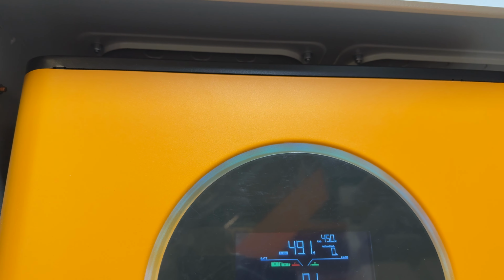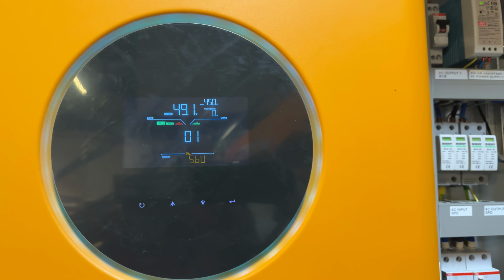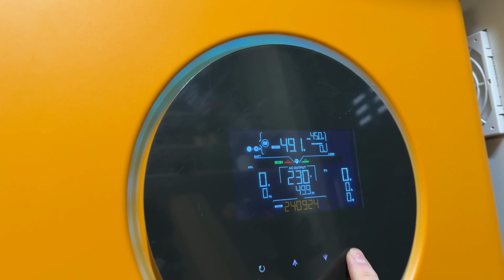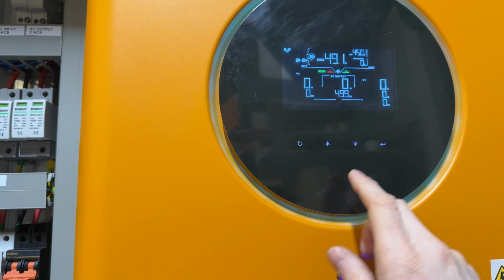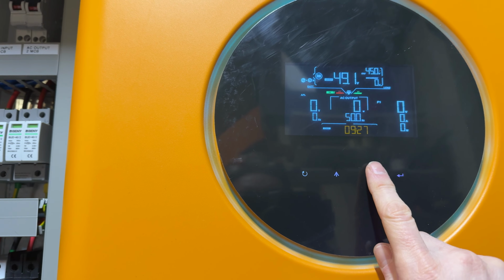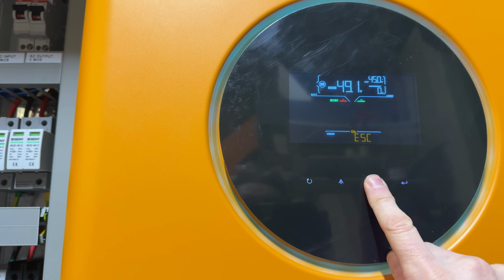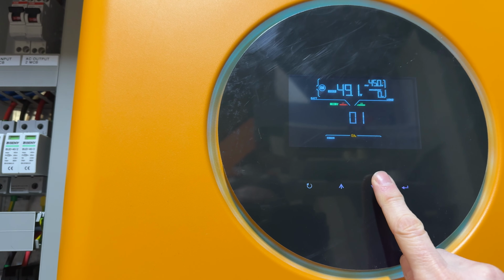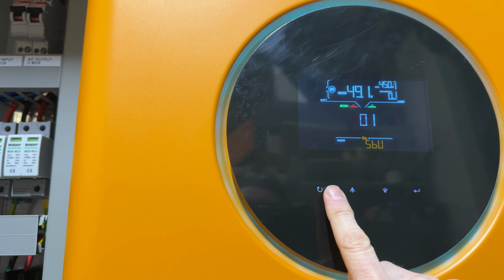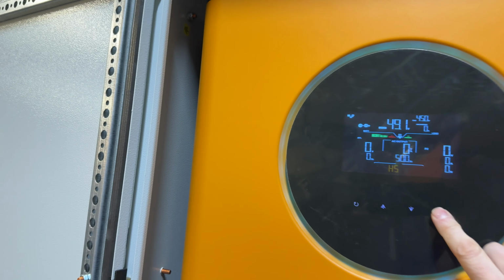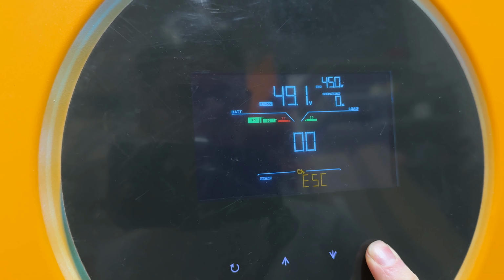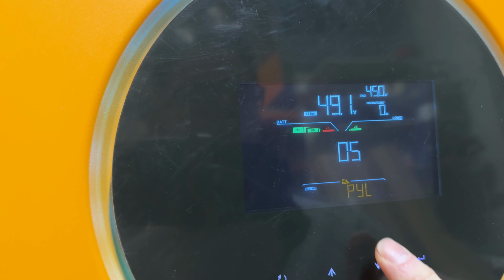The most common type of operation is solar, battery and utility. And I have to apply the same on the slave inverter. Whatever changes you make on inverter 1, you have to apply on inverter 2 as well. So let's enter the menu here and show you how it works. That's it. Now on the master inverter, menu 5 is a very important parameter. In menu 5, it must be set to PYL, that means Pylontech.